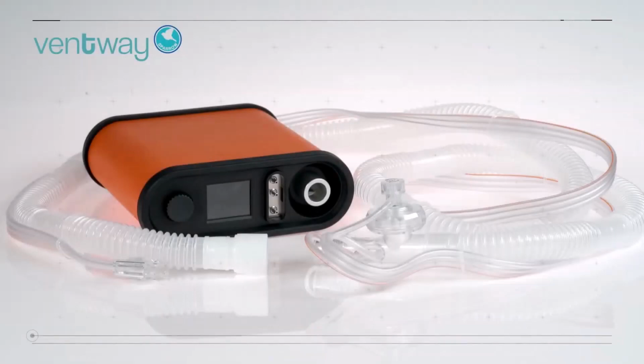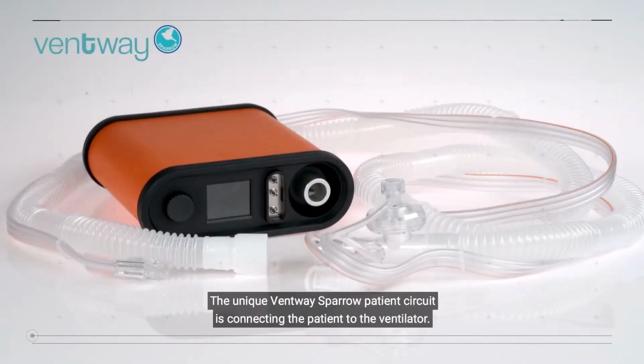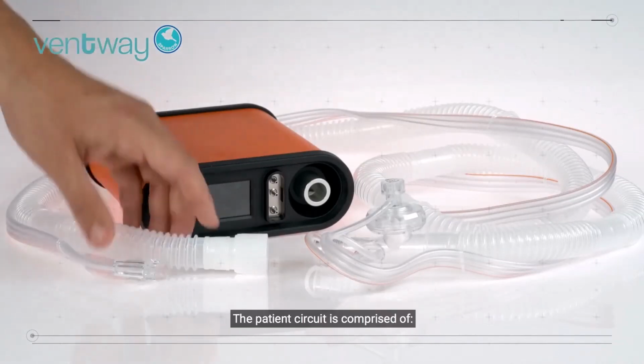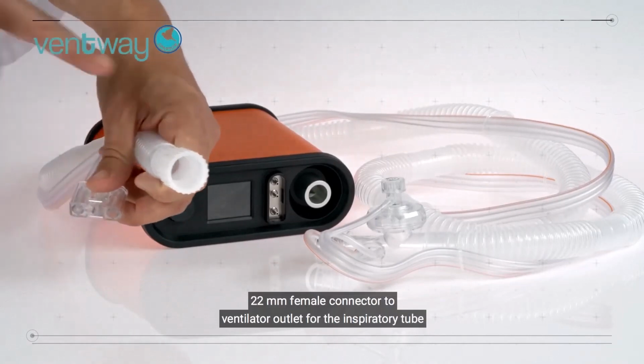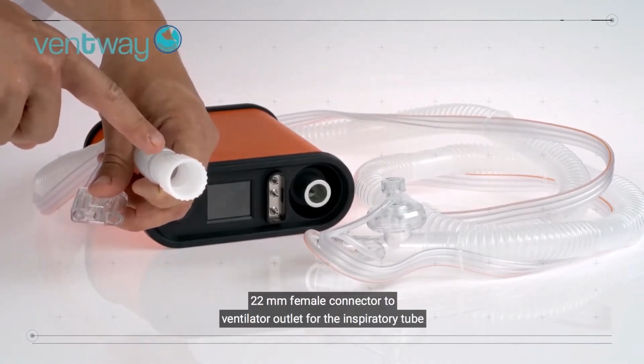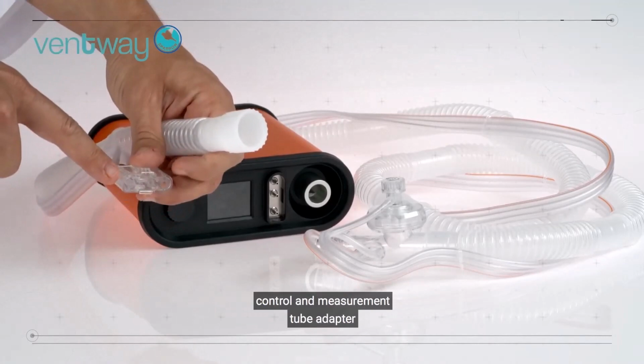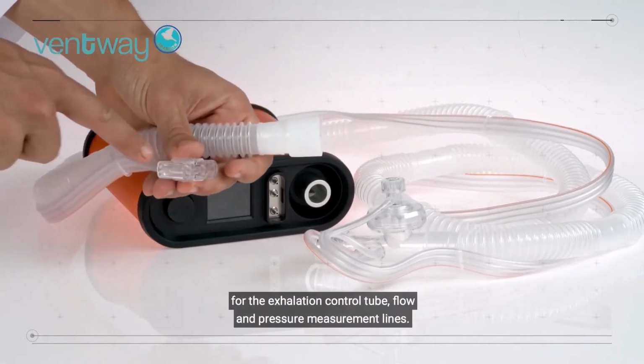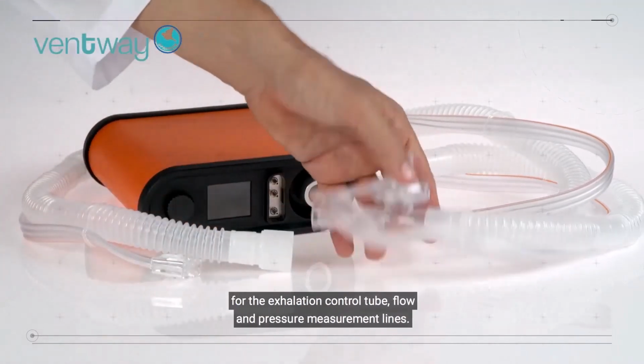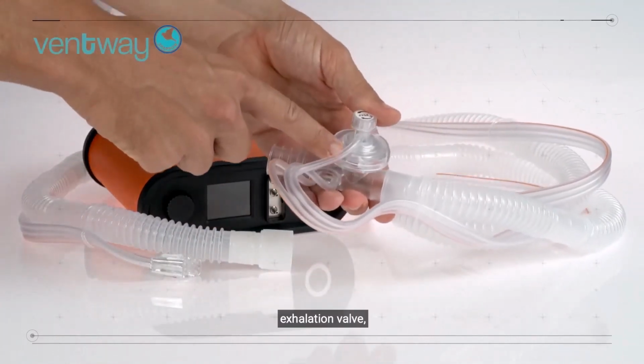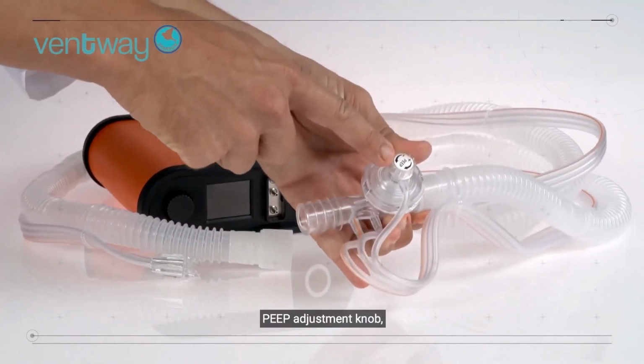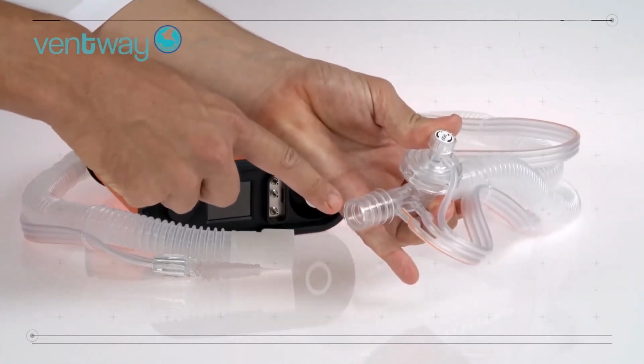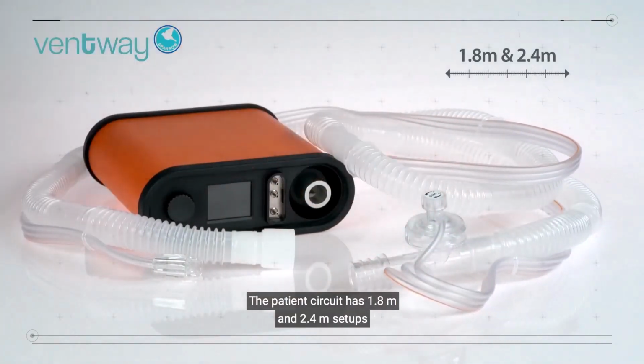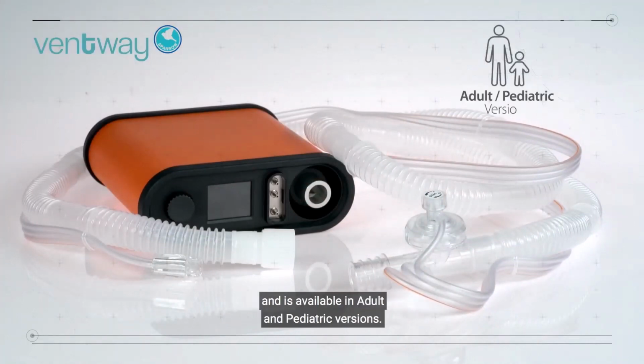Patient circuit. The unique Ventway Sparrow patient circuit is connecting the patient to the ventilator. The patient circuit is comprised of 22 mm female connector to ventilator outlet for the inspiratory tube, control and measurement tube adapter for the exhalation control tube, flow and pressure measurement lines, exhalation valve, PEEP adjustment knob, patient connection. The patient circuit has 1.8 meter and 2.4 meter setups and is available in adult and pediatric versions.